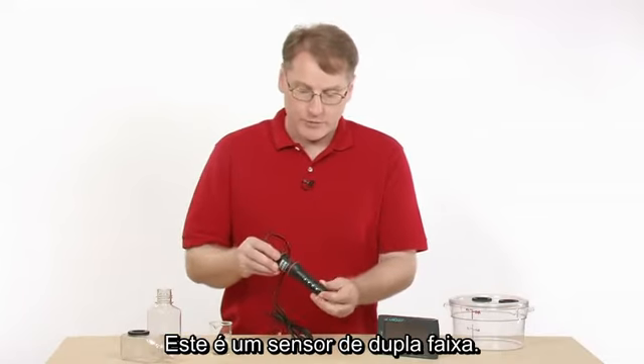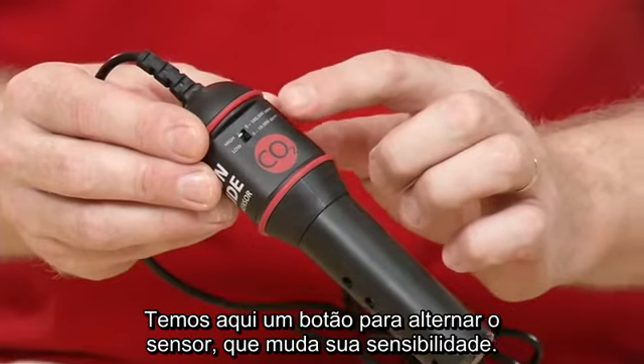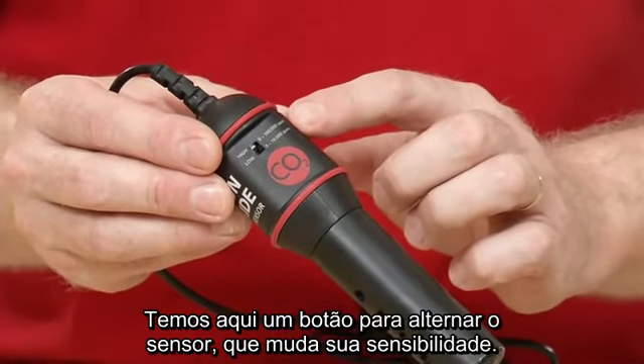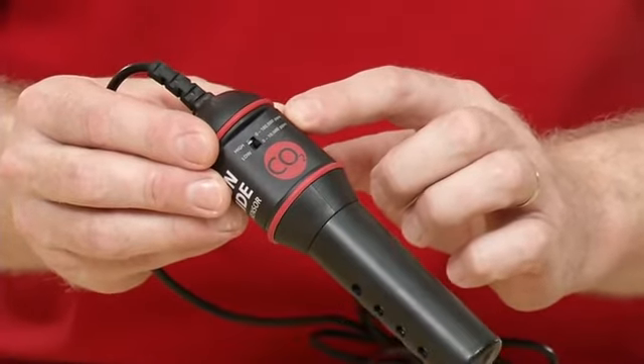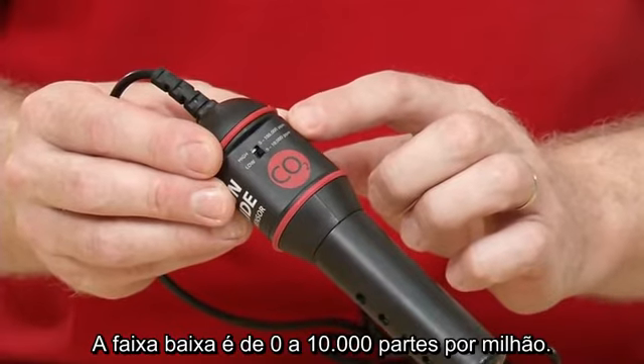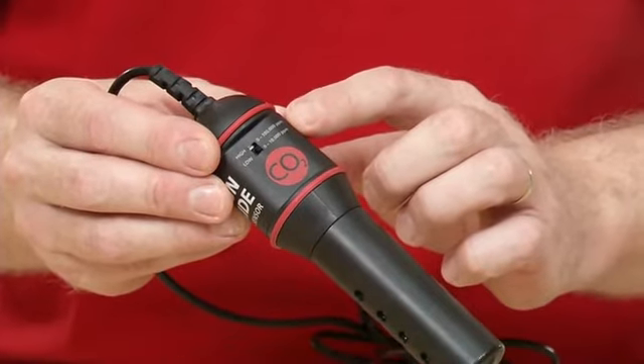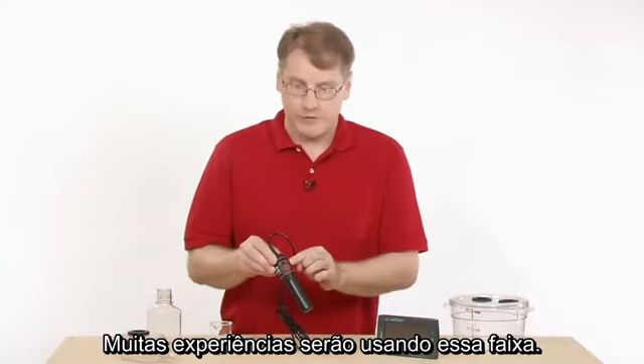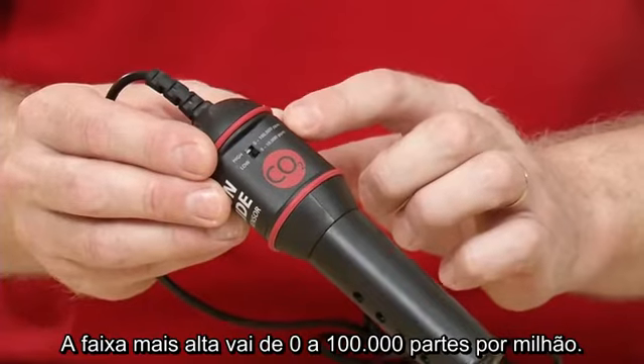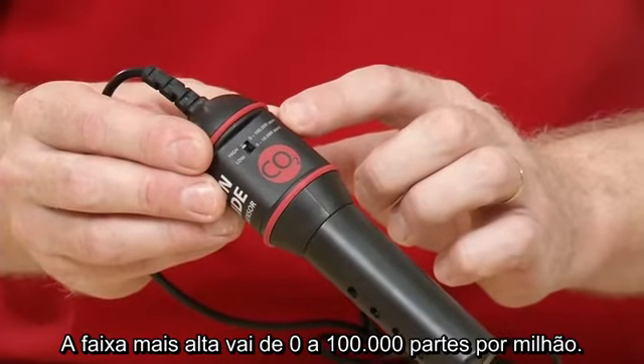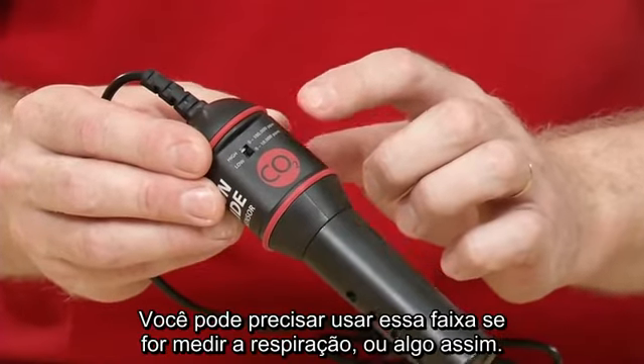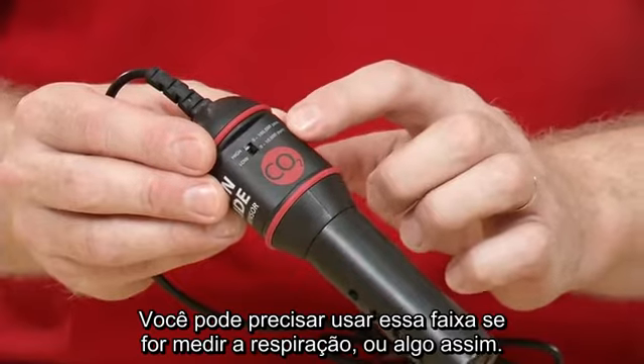Now, this is a dual range sensor, and so there's a sensor setting switch here, so it's a sensitivity switch. The low range is 0 to 10,000 parts per million. A lot of the experiments will use that. And then the higher range is 0 to 100,000 parts per million. You might need to use that if you're going to breathe on it or something like that.